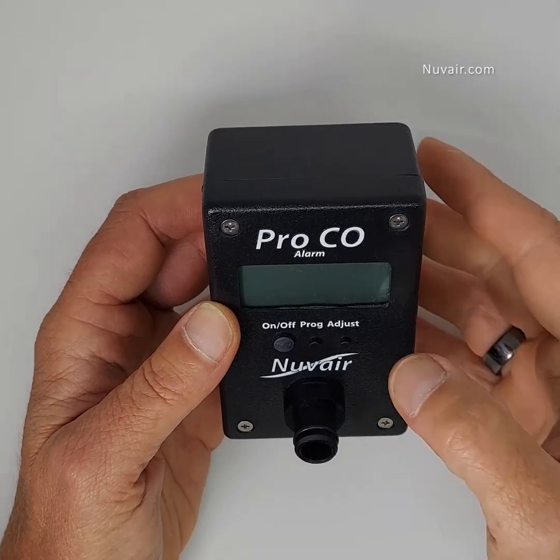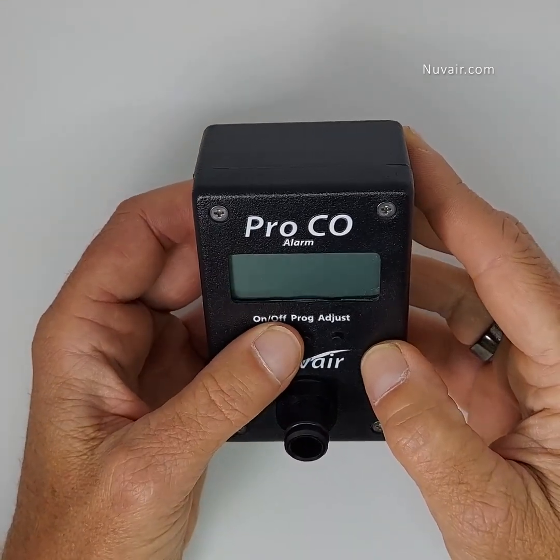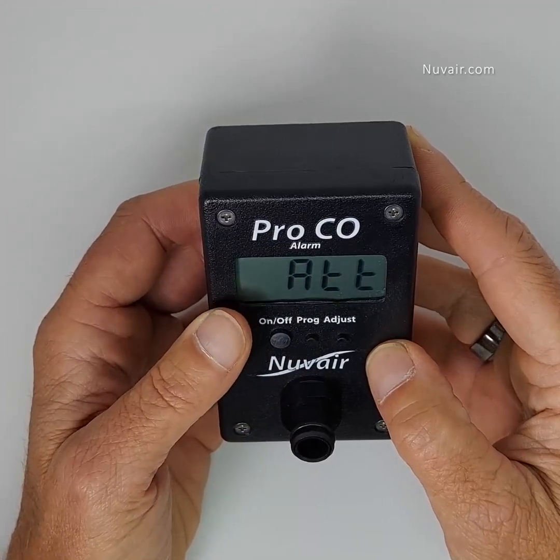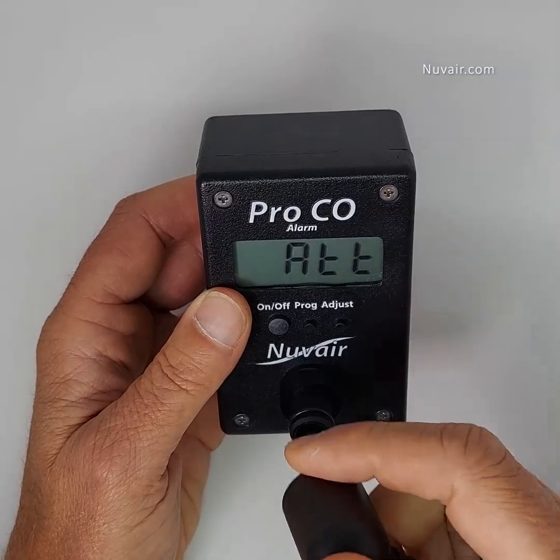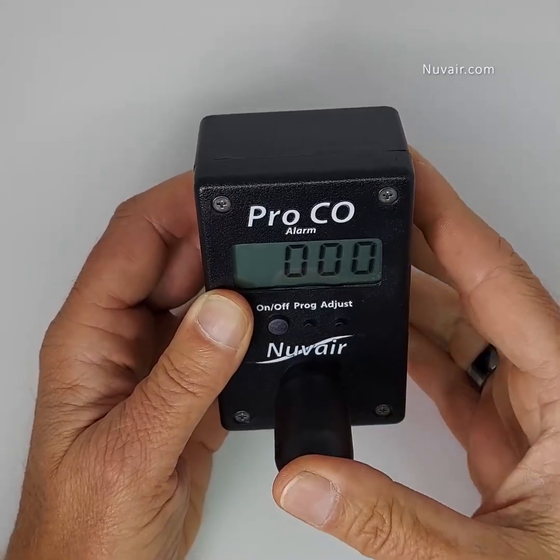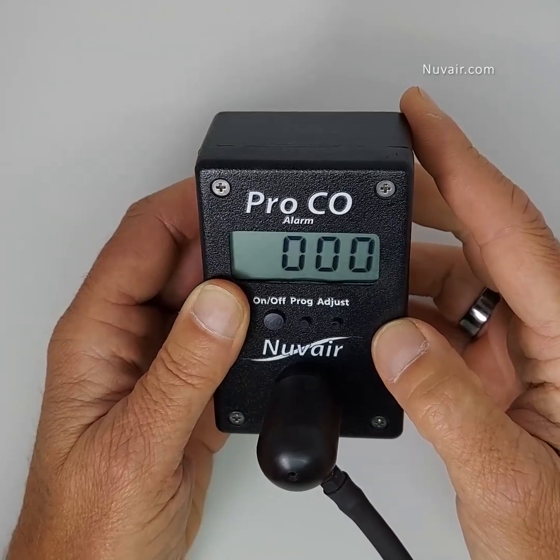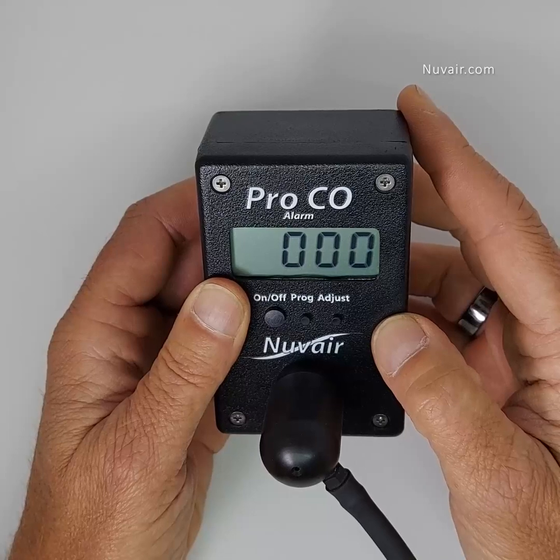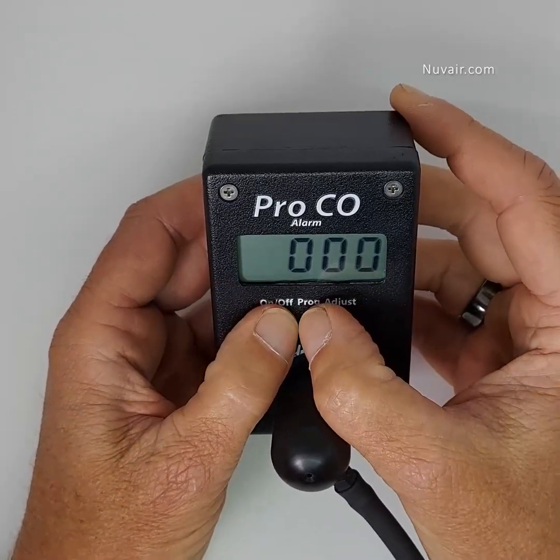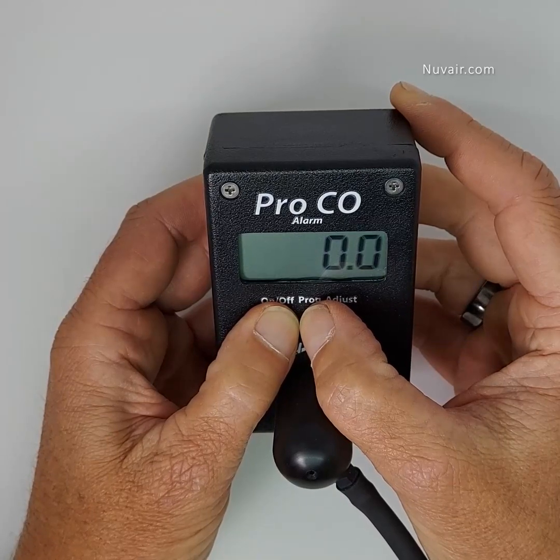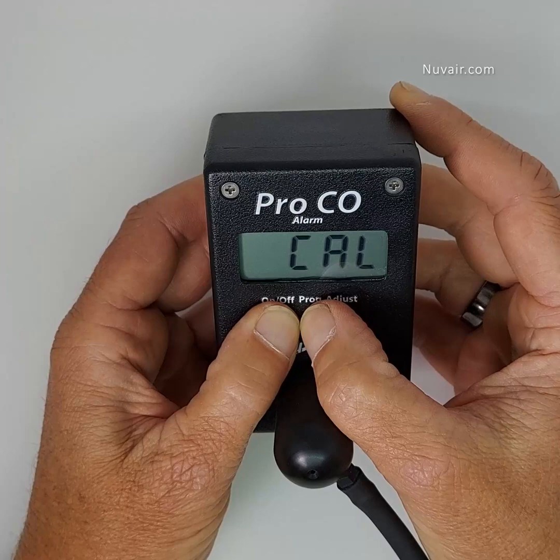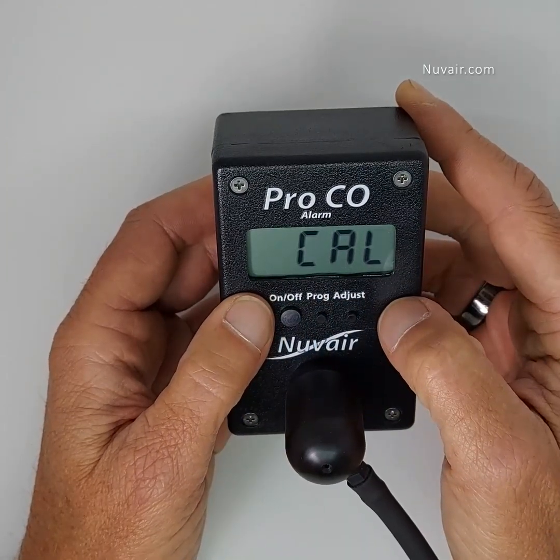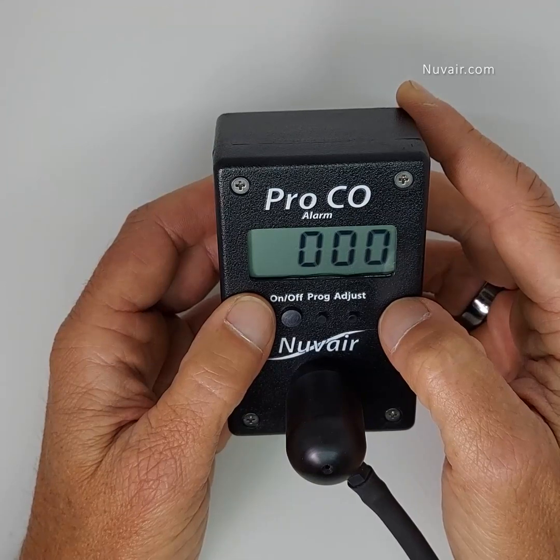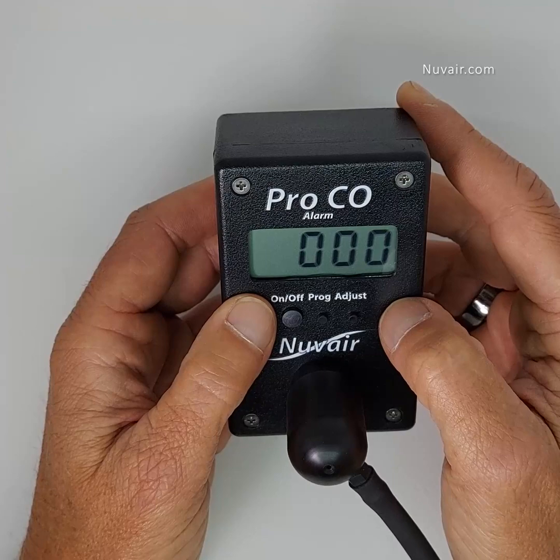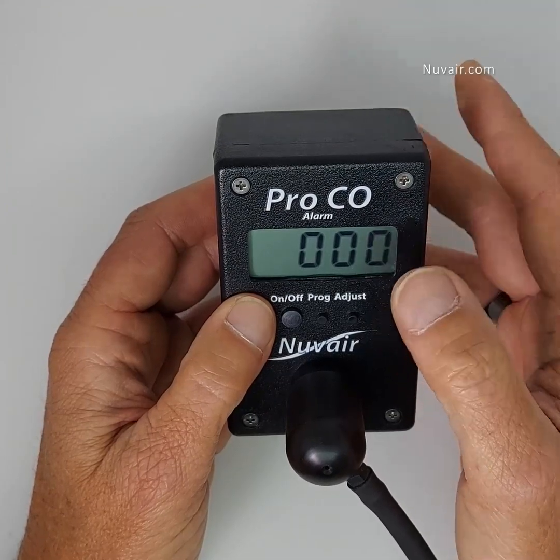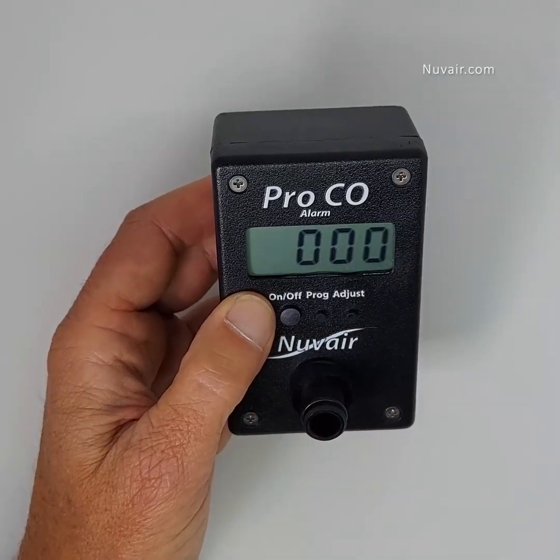To calibrate the analyzer 0, follow these 4 steps. Step 1. Turn on the analyzer. Step 2. Attach a flow of certified test gas, containing 0 parts per million carbon monoxide, 100% nitrogen, regulated to 0.5 to 3 liters per minute. Step 3. Press the on-off and program button simultaneously, and hold until the display flashes CAL. Step 4. When the display returns to a reading of 000, the analyzer 0 has been set. If your analyzer is equipped with a lithium battery, read and understand all instructions included with a battery charger.